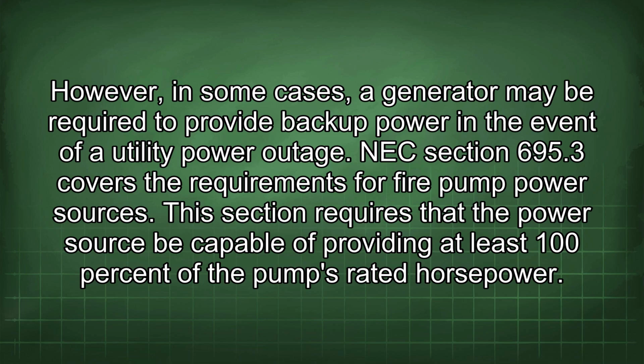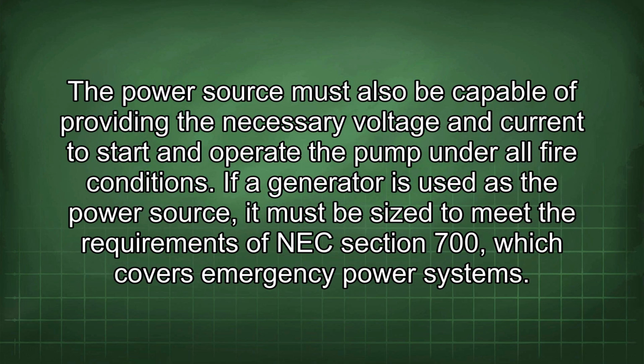NEC Section 695.3 covers the requirements for fire pump power sources. This section requires that the power source be capable of providing at least 100% of the pump's rated horsepower. The power source must also be capable of providing the necessary voltage and current to start and operate the pump under all fire conditions. If a generator is used as the power source, it must be sized to meet the requirements of NEC Section 700, which covers emergency power systems.